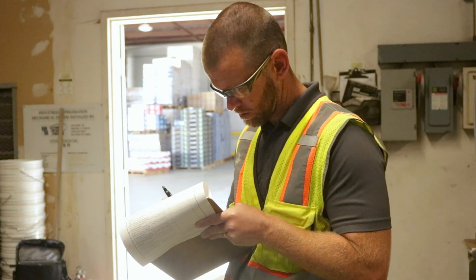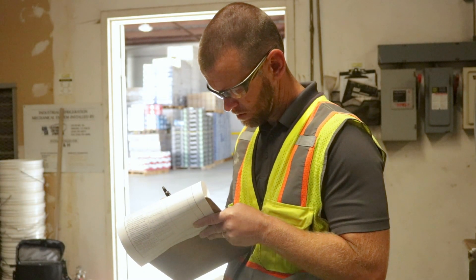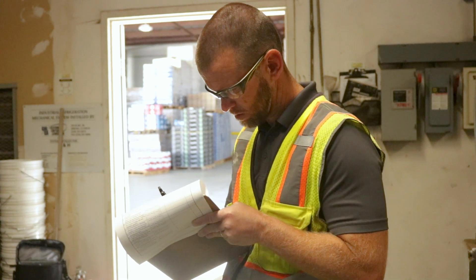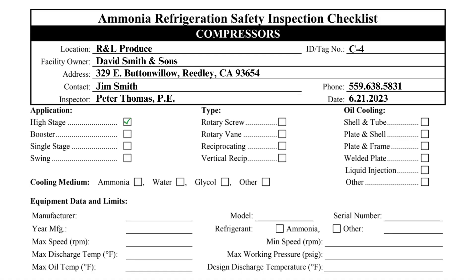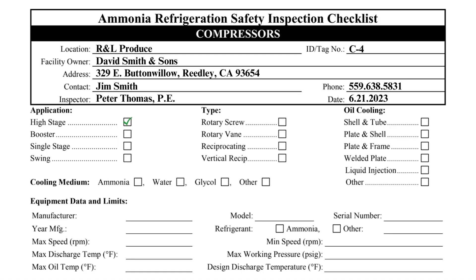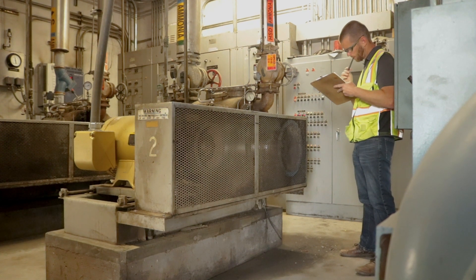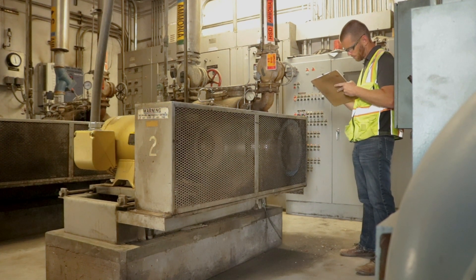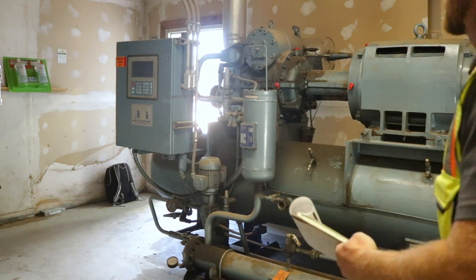Next, the inspector should indicate on the inspection checklist the application of the compressor. This compressor is a high-stage compressor, so the appropriate box should be checked. The type of compressor must also be indicated by checking the appropriate box. In this video, we will provide examples of inspecting both reciprocating and rotary screw compressors.